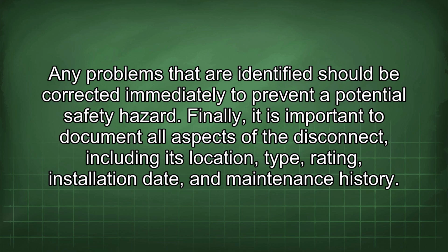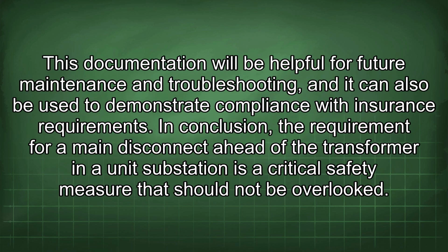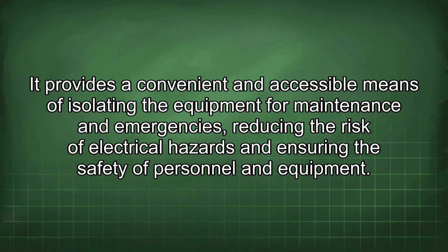Finally, it is important to document all aspects of the disconnect, including its location, type, rating, installation date, and maintenance history. This documentation will be helpful for future maintenance and troubleshooting, and it can also be used to demonstrate compliance with insurance requirements. In conclusion, the requirement for a main disconnect ahead of the transformer in a unit substation is a critical safety measure that should not be overlooked. It provides a convenient and accessible means of isolating the equipment for maintenance and emergencies, reducing the risk of electrical hazards and ensuring the safety of personnel and equipment.